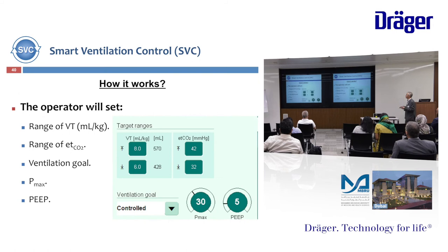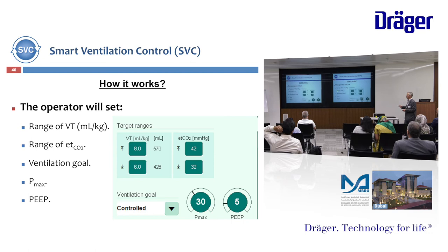Smart ventilation control is a system designed to deliver knowledge-based strategic closed control loop automation of minute ventilation. Knowledge-based means the stored algorithms are based on data extracted from experts — from all of you — and behavior in specific situations. Smart ventilation control operates as pressure controlled or pressure support mode. How it works: the operator sets a range of tidal volume, which can be by default from 6 to 8 or from 4 to 9 mL/kg. The operator also sets a range of end-tidal CO2, which can be modified. The default depends on your target of ventilation.